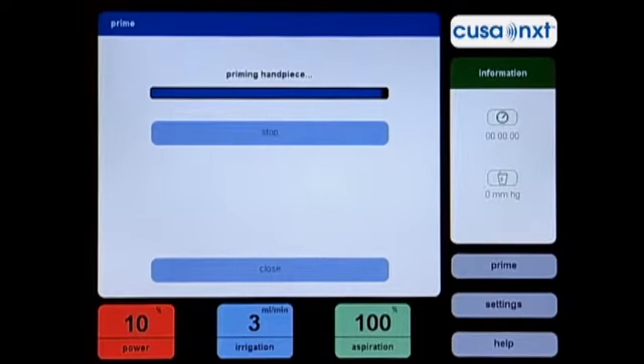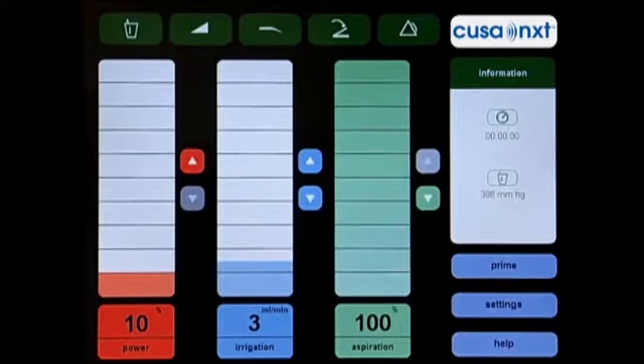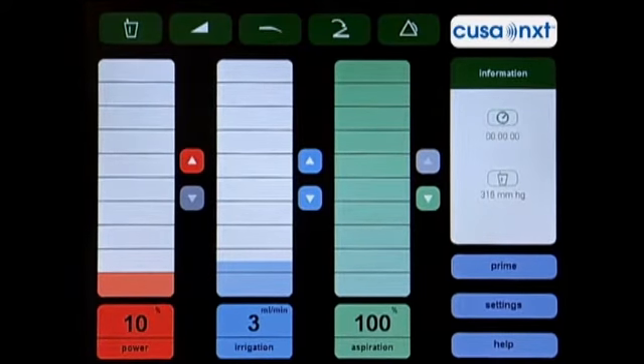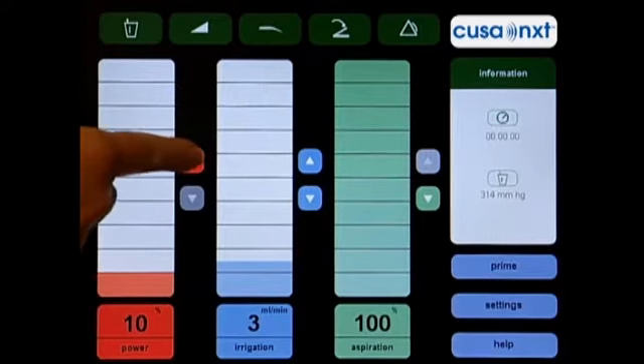Once priming is complete, you will see the main system screen. It will display the default settings of 10% power, 3 milliliters per minute of irrigation, and 100% aspiration, unless different preset values were previously saved. The CUSA NXT is now ready for use by the surgeon. You may use the touchscreen monitor to adjust the power, irrigation, and aspiration levels.